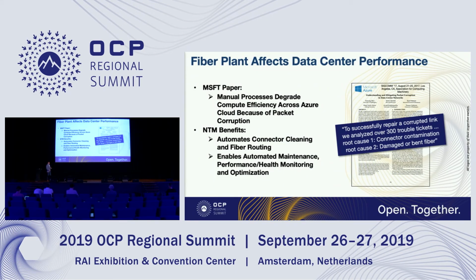This is an interesting paper from Microsoft, which didn't actually talk about automation of the physical layer, but it points out that when they looked at trouble tickets leading to packet corruption in their Azure data centers, it's surprising, the number one cause of problems was connector contamination. The number two was damaged or bent fiber. So really pretty mundane things that most people tend to not be too focused on. So it really shows that manual processes can degrade the compute efficiency dramatically.